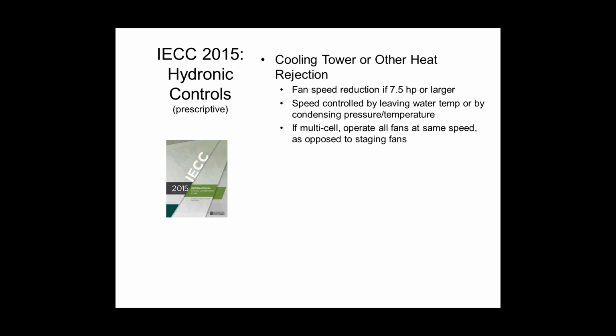On the hydronic side, still from a controls perspective, if you have a cooling tower or a dry cooler or something like that, plan on controlling fan speed on those. If you have 7.5 horsepower motors or larger, which is pretty big, but you'll definitely have cooling towers that have that. You can do it based on leaving water temperature if you choose. We at Carrier and TEC oftentimes prefer that you do it off of what we call the head pressure reference signal, which is what the code refers to as the condensing pressure and temperature signal. So the chiller basically tells the cooling tower when it needs less capacity, right?